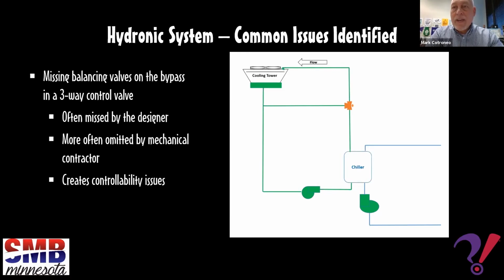But when it comes down to the end of the project, as far as operationally is concerned anyway, the TAB certainly picks up a lot of the first things that have issues. Things like missing dampers, missing valves, that kind of thing. And then commissioning comes back, and they can really find out that a lot of the control isn't there either. So yes, it is an issue on projects, and hopefully everybody's working on their own, not just waiting for TAB or commissioning to pick up all the issues.